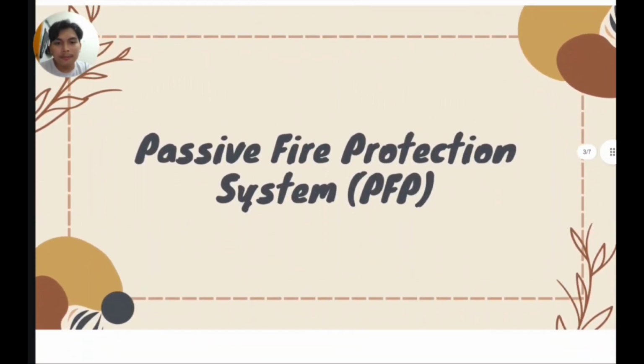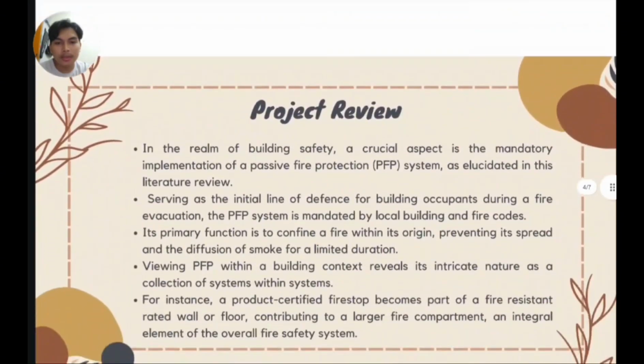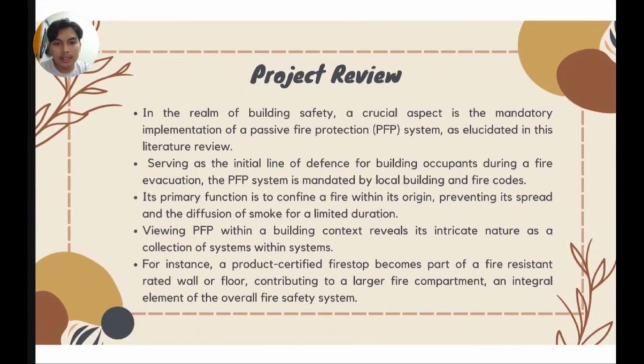Okay, now we move to the passive fire protection system, PFP. Project review. In the realm of building safety, a crucial aspect is the mandatory implementation of a passive fire protection (PFP) system, which is elucidated in this literature review, serving as the initial line of defense for building occupants. During a fire evacuation, the PFP system is mandated by local building and fire codes. Its primary function is to confine a fire within its origin, preventing its spread and the diffusion of smoke for a limited duration. Viewing PFP within a building context reveals its intricate nature as a collection of systems within systems.